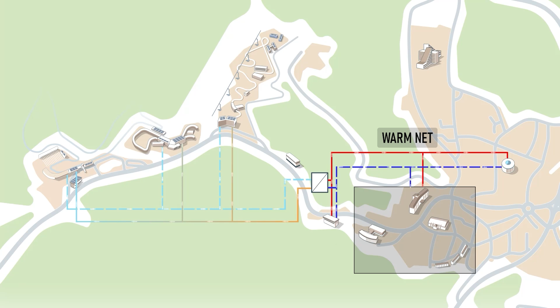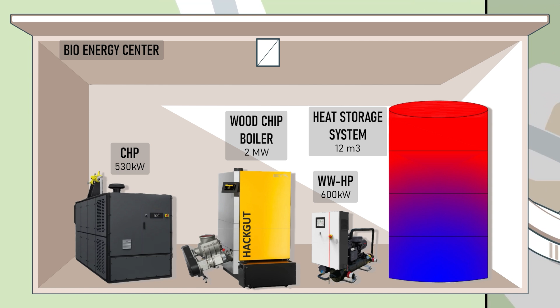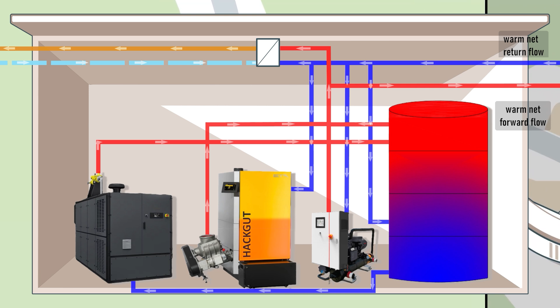The centerpiece of the warm network is the Bioenergy Center. This center combines a combined heat and power unit, or CHP, a heat storage system, a wood chip boiler using resources from Thuringian forests, a large heat pump, and a heat exchanger. The CHP and the wood chip boiler account for the majority of the heat supply.